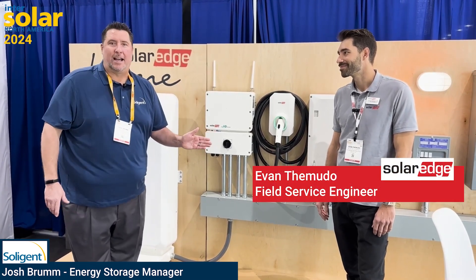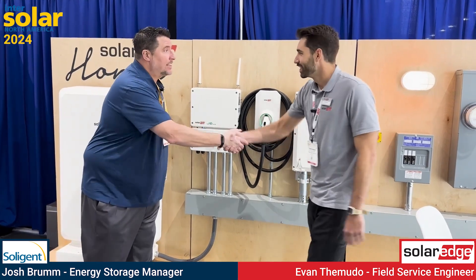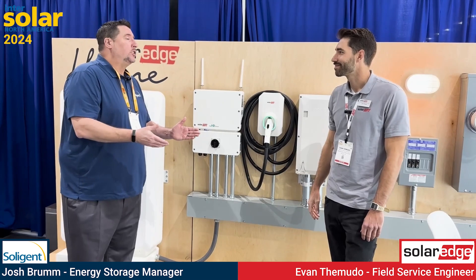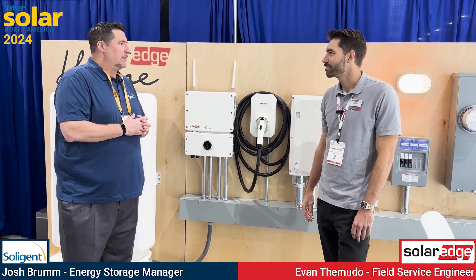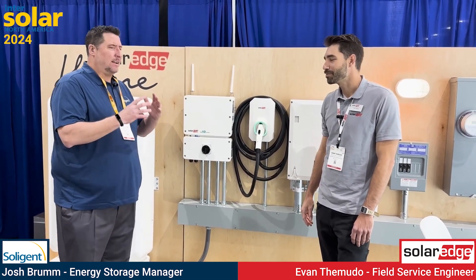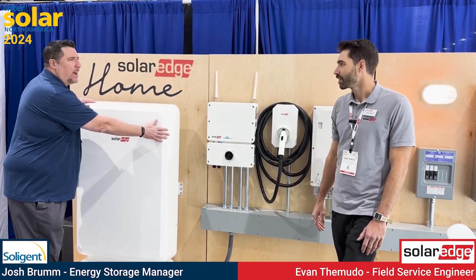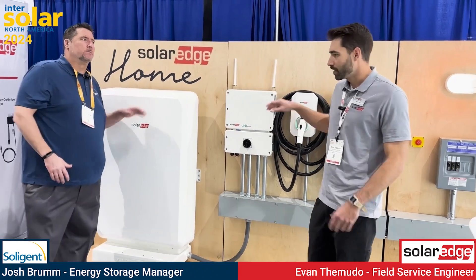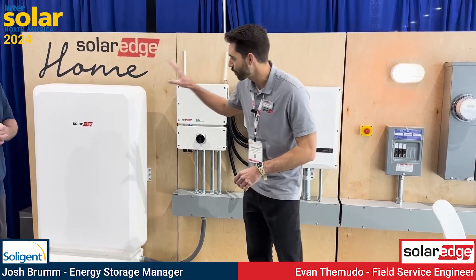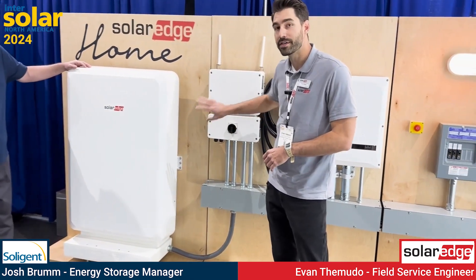Evan Themudo with SolarEdge is with us here at booth 1215 at Intersolar. Main panel upgrade avoidance is so valuable. Talk a little deeper about it — how many batteries can we have on that 40-amp breaker per inverter with an EV charger? Because this is a DC-coupled system, you can have up to three batteries on one inverter. They land directly into the inverter on the DC side.